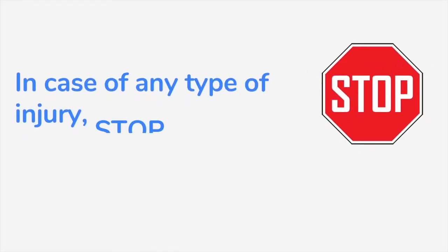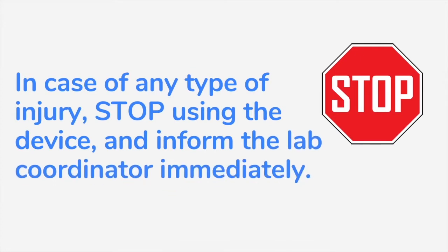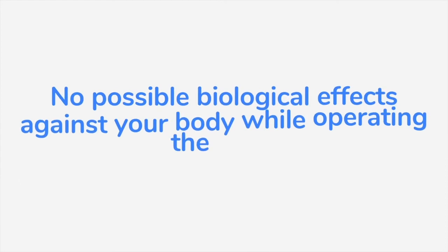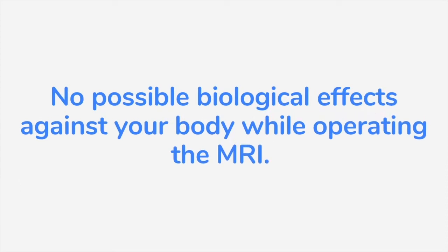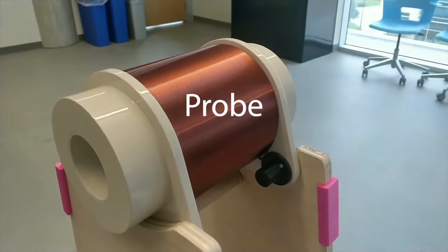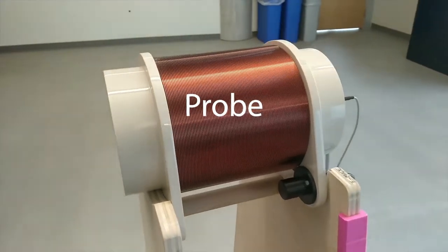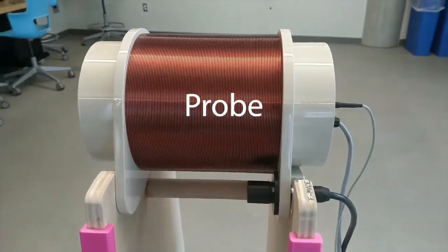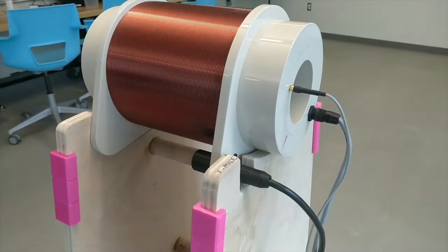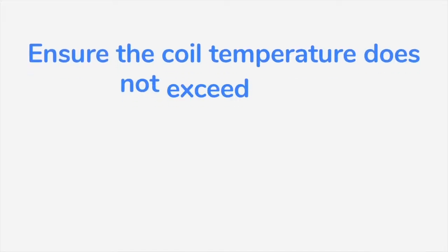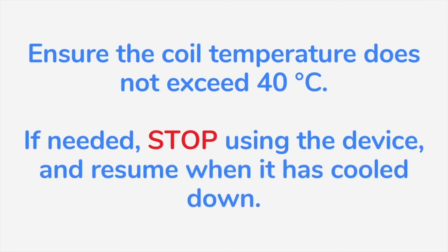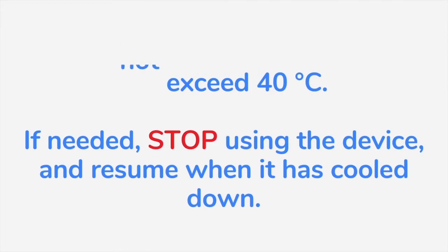In case of any kind of injury, stop using the device and inform the lab coordinator immediately. There won't be any kind of biological effects against your body while operating this device. The probe, which is pictured as the brass coil, could get warmer when used for prolonged periods. Ensure that the coil is not getting warmer than 40 degrees Celsius and stop using the device if needed and resume when it's cooled down.